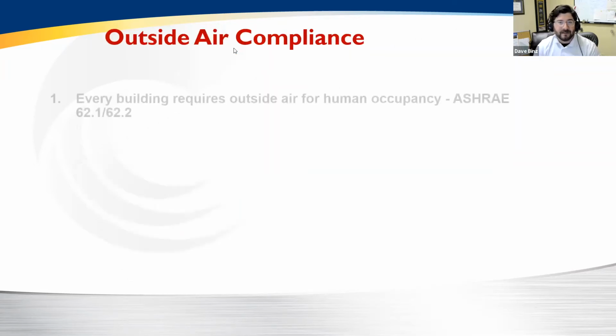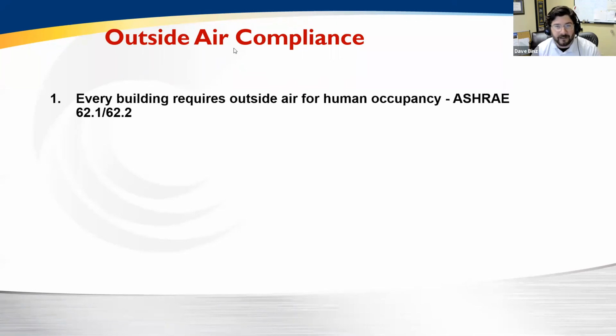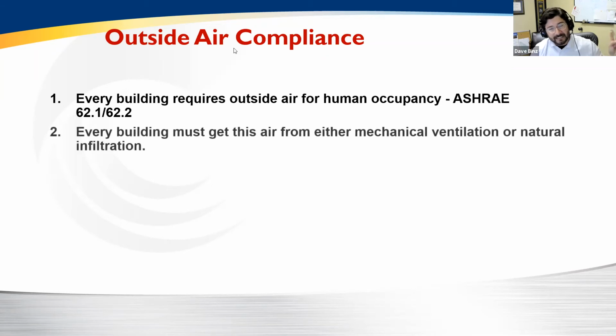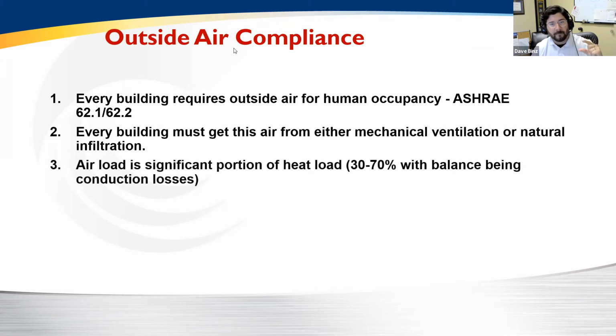Well, as engineers, we know that every building must have ventilation if it's designed for human occupancy, right? So we have this beautiful standard, ASHRAE 62.1, which gives our engineering community guidelines to help make sure that indoor air quality is good and safe. Secondly, this air must come either through natural infiltration or mechanical ventilation. And sometimes in large warehouses and large distribution centers, there can be a balance of ventilation and infiltration. When we look at those two key components, that's what makes up the total air load of our building.